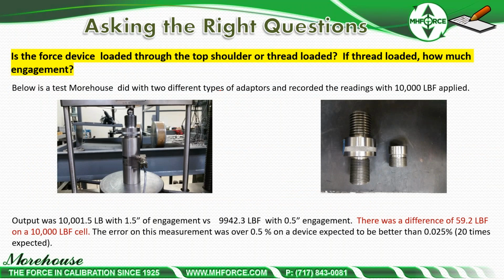And here's what we did. Here's a simple test. This is a load cell, a rather good load cell. Output was 10,001.5 pounds with 1.5 inches of engagement. It was 9942.3 with 1/2 inch engagement.